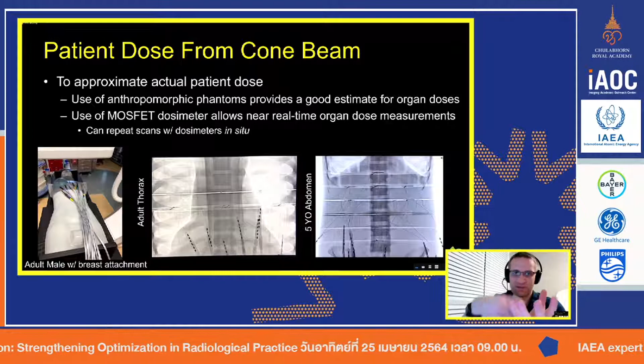The nice part about this is I can do a bunch of measurements in these phantoms, so I can get organ doses, and that really gives me a better understanding of how much radiation a patient, if they were of this same size, how much they would receive. And so it gives me a better idea of risk and patient dose. It's not true patient dose. The other option would be to use really high-end software called Monte Carlo, where you would take the actual patient images and do a lot of calculations on it, and it could tell you what the organ doses are.